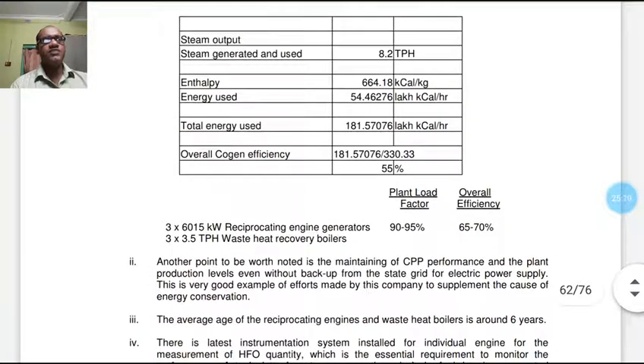Steam output: steam generated and used 8.2 TPH, enthalpy 664.18 kilocalorie per kg, energy used 54.46276 lakh kilocalorie per hour, and total energy used 181.57076 lakh kilocalorie per hour. So we can find that total cogeneration efficiency is nearly 55%. The plant load for engine and waste heat recovery boiler, the load factor is 90 to 95%, and overall efficiency varies from 65 to 70%.